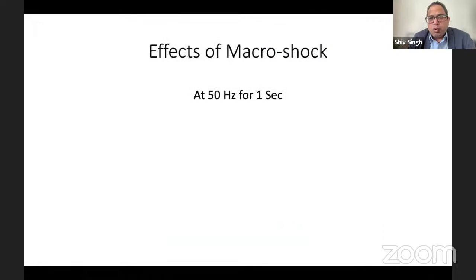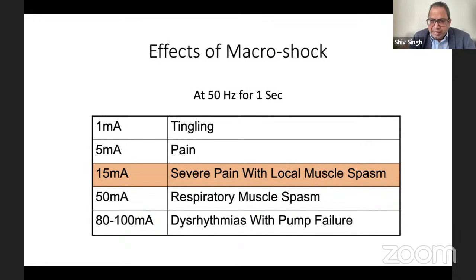Okay. So what amount of current flows through you determines what you'll feel. You may not feel anything at all, or you can get a tingling sensation, or it can even lead to death. Okay. So what happens if 240 volts or 230 volts at 50 hertz passes through for 1 second? Like say 1 milliamp and above, we call tingling sensation. 5 milliamps can cause pain. 15 milliamps leads to severe pain with local muscle spasm. 50 milliamps can cause respiratory muscle spasm. So slow death, asphyxia. Whereas 80 to 100 milliamps will lead to dysrhythmias with pump failure.